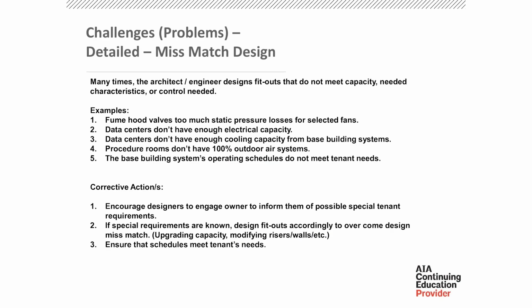So that's the design for the fit out. Many times the architect/engineer designs fit outs that do not meet the capacity or control characteristics needed. For example, I discussed earlier, if you have a tenant that has fume hoods, their valves might have too much static pressure loss for the fans. Data centers don't have enough electric capacity. Data centers don't have enough cooling capacity for the base building systems. Procedure rooms don't have 100% outdoor air systems. Base building systems operating schedules do not meet tenant needs.